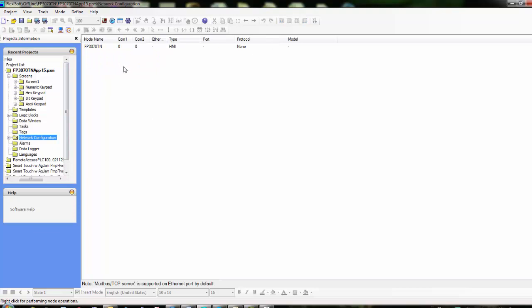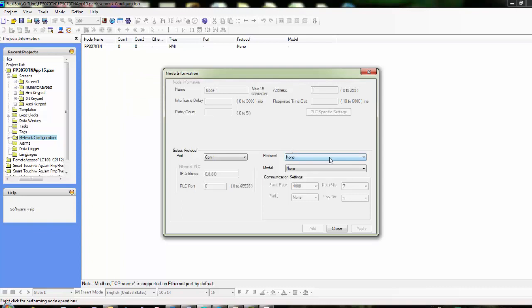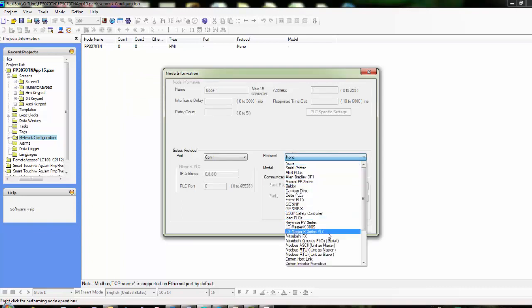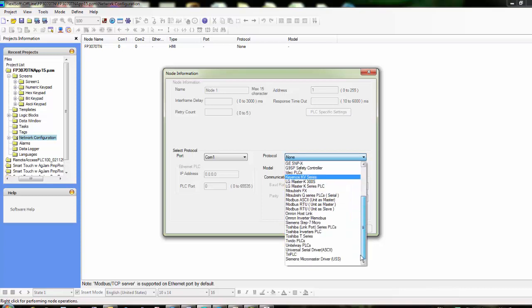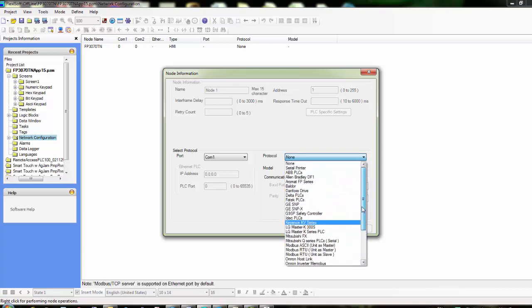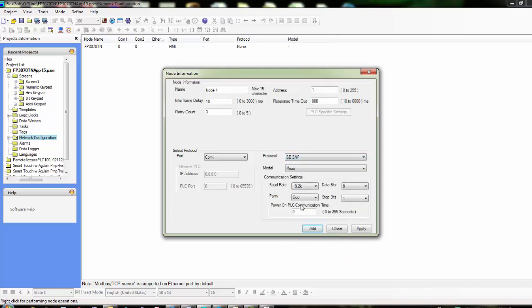In this blank space we're just going to right-click and then click Add. For the protocol, you can see we have a pretty extensive list of protocols that we support. For the GE, you can see that we have GE SNP or GE SNP-X. For this application we'll just choose the SNP. Once we've chosen that, we can give it a node address, a response timeout, interframe delay, and retry count.